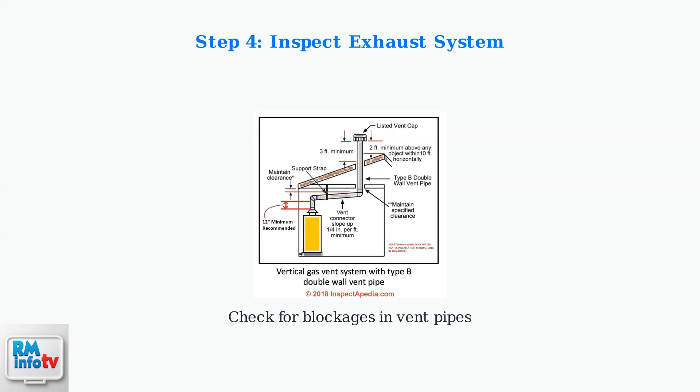Inspect the exhaust and vent pipes for any obstructions. This diagram shows a proper gas vent system. Make sure the vent pipe is clear and properly supported, with no debris blocking the airflow.